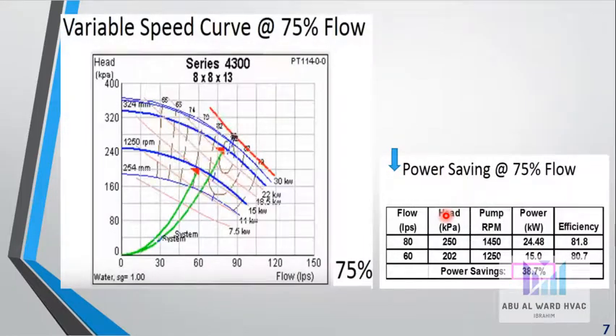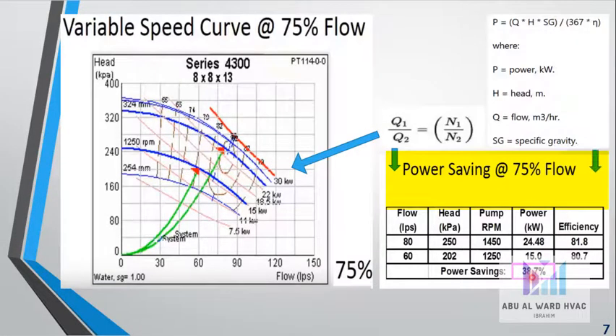If we reduce the flow up to 75%, from 80 to 60 for example, we will reduce the head and pump RPM. Thus we can reduce the pump power according to the formula, which will have power savings of 38.7%.